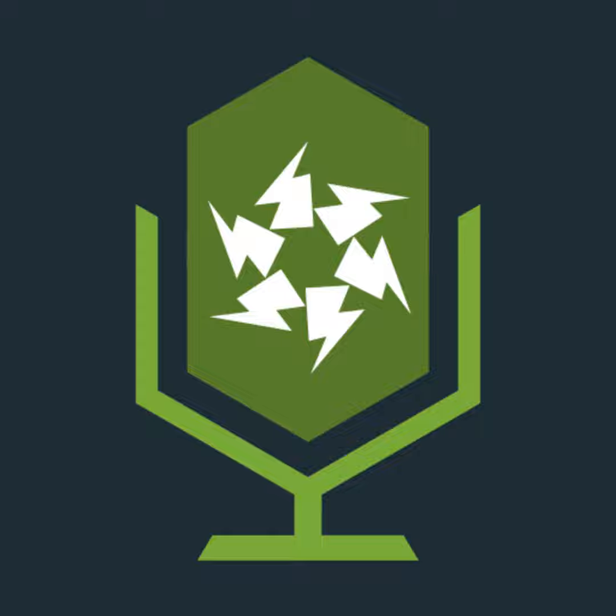So a final circuit for 63 amp for one or more socket outlets, that's actually increased. That's increased from what it used to be. So obviously we can have socket outlets, plug and socket outlets, 32 amp and 63 amp. So they've now gone up to the 63 amp one. I can understand why. It's a regular point of utilisation. I see that a lot in the food industry where I do work. But it's a socket outlet circuit. So a 63 amp socket outlet, single phase or three phase.